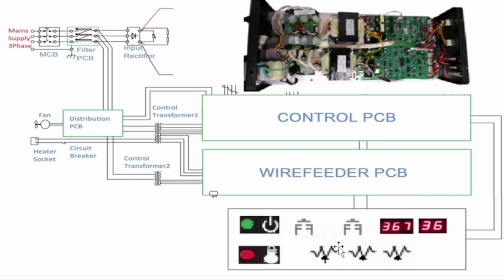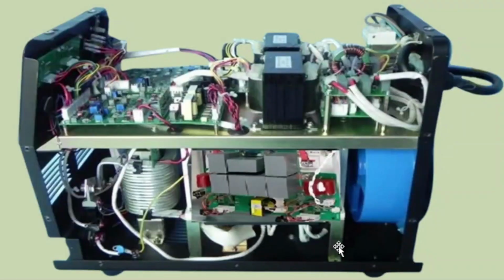Next to see lower part of the machine. 4 IGBTs are connected in full bridge configuration mounted on the heatsink. From IGBT's connections are going to primary of the amorphous core main transformer. Secondary of the main transformer is in center tap configuration. Center tap of the transformer is going to iron core choke. From choke, connection is going to a shunt for welding current monitoring. From shunt, it is going to negative output terminal of the machine. Proportional current feedback from shunt and voltage feedback across output terminals are going to control PCB.